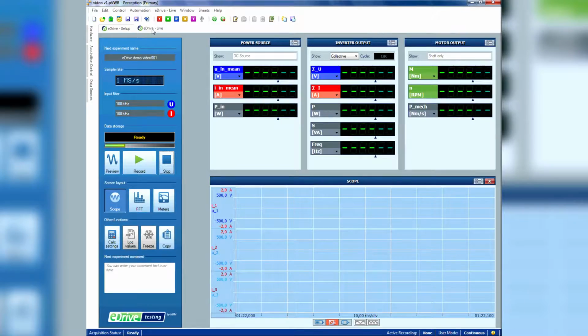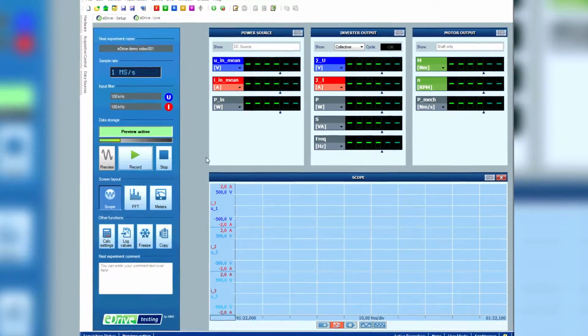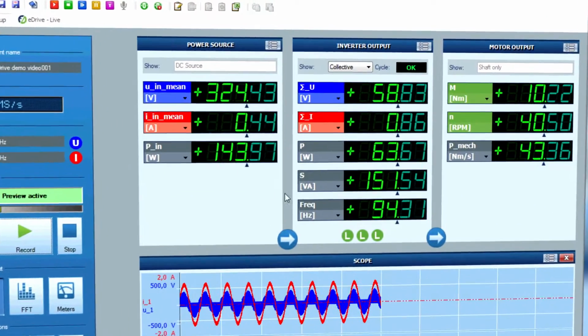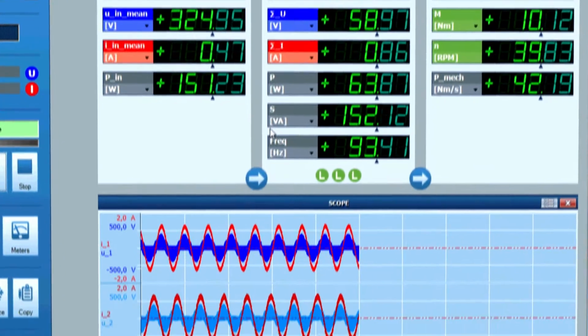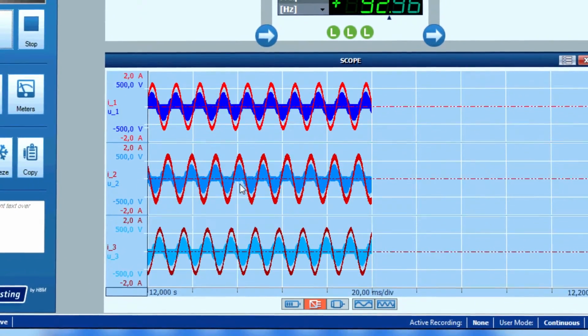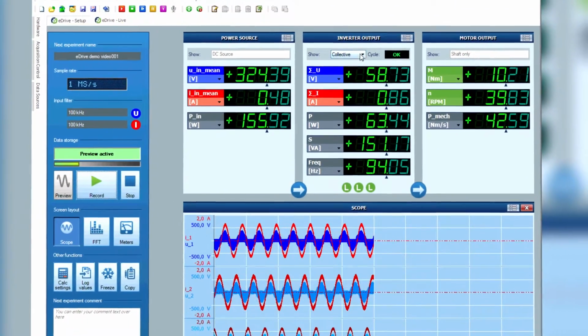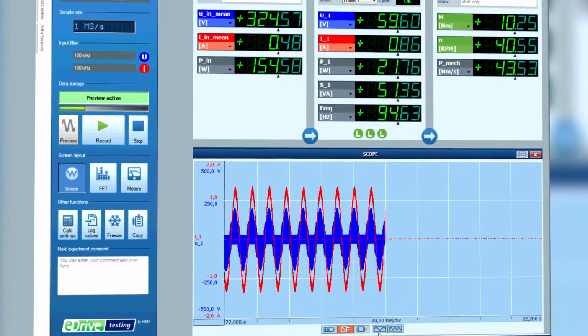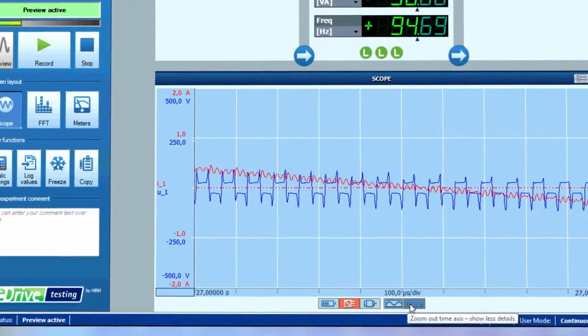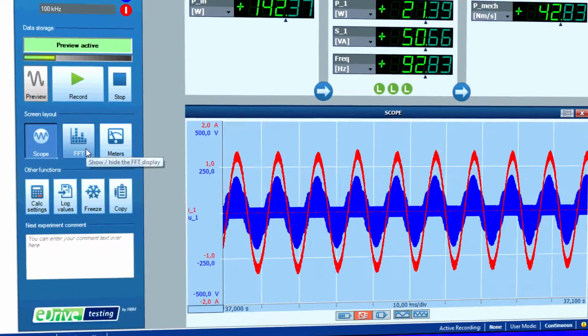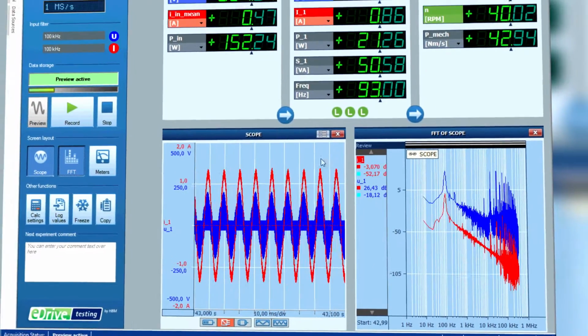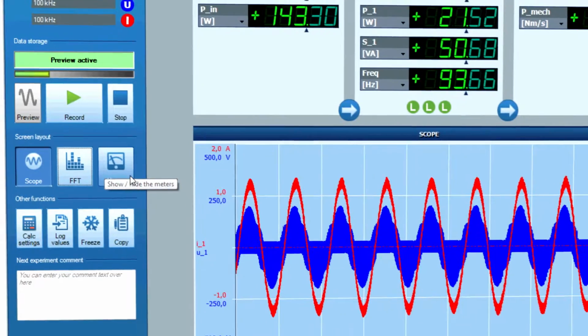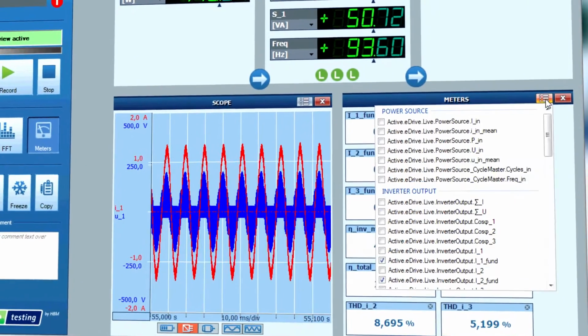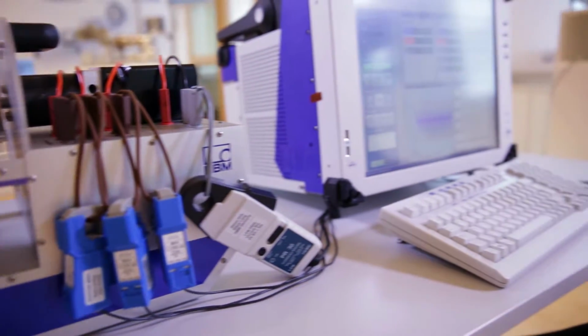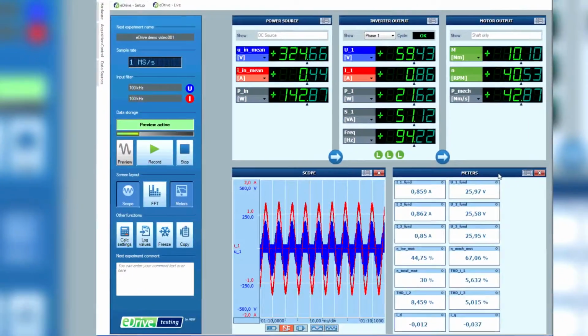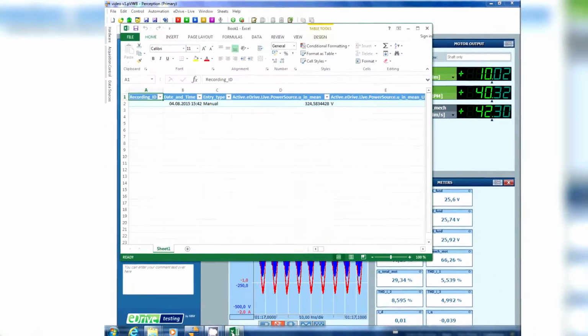The live sheet of the software shows traces and numerical results. In the upper half of the 17-inch display, meters are showing results similar to a power analyzer, and in the lower half, there is a scope-like waveform display. The scope can be set to different input signals or to individual phases, tracing the setting of the power meters. Zooming in on the waveform displays additional signal details if needed. An FFT display shows fundamental and switching frequencies at a glance. For more results, a configurable section with more meters is available. Here, over 50 computed parameters can be selected for live display. At any time, the Log to Excel button transfers all results straight into Excel. No storage, no conversion, no export.